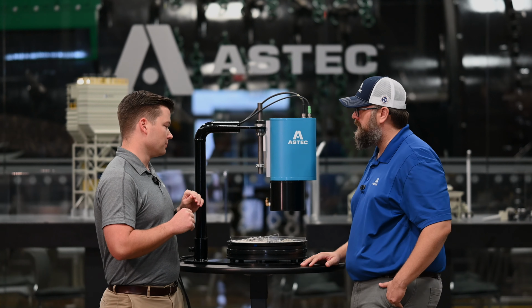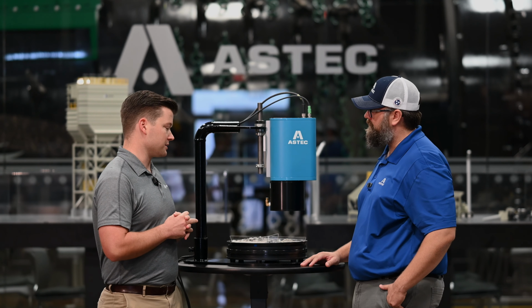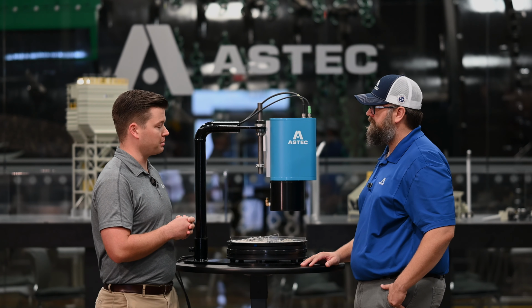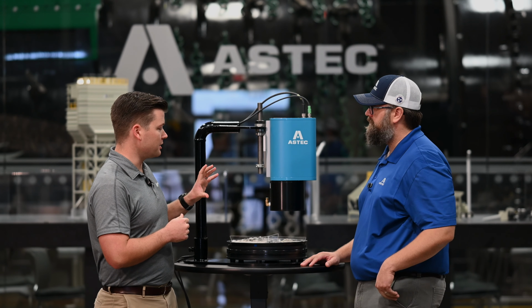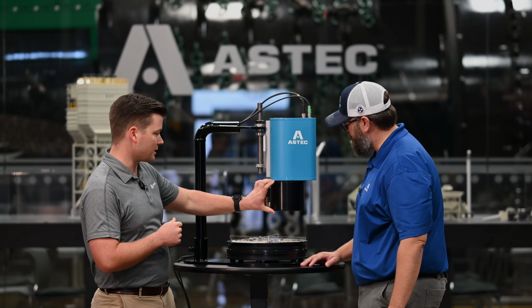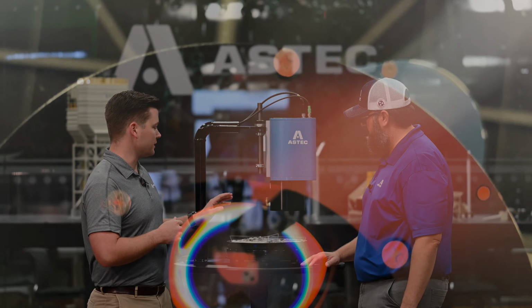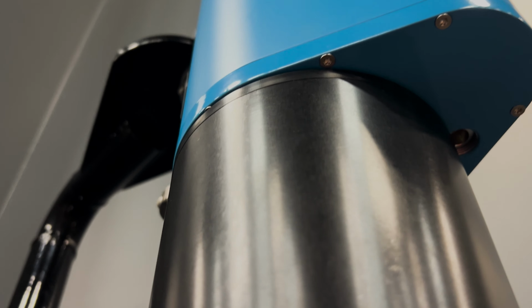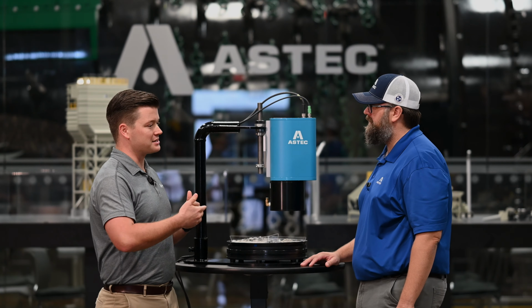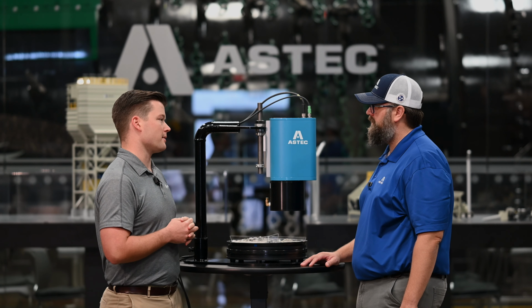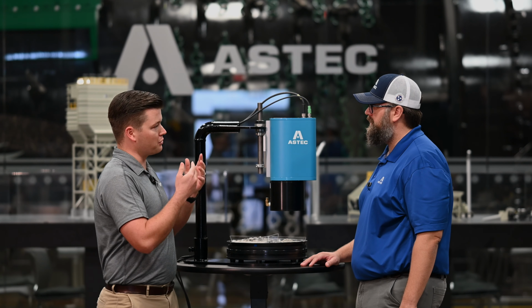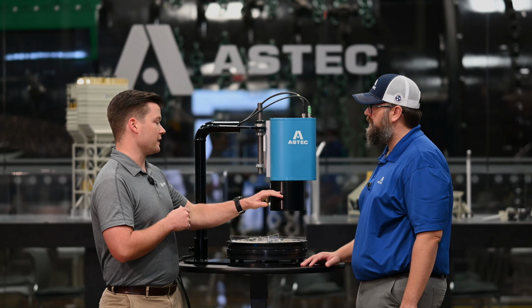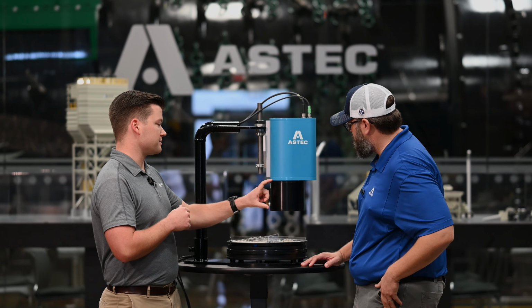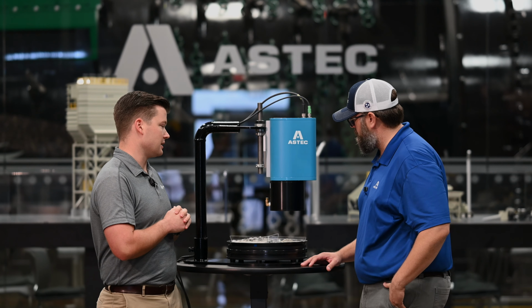The thing that impressed us most about this sensor was how rugged and survivable it is in an asphalt plant environment. One big contributor is this black portion at the bottom, which is actually a dust shield. We feed compressed air into a collar at the bottom of the sensor, providing a positive pressure environment just past the lens, which keeps dust, moisture, and other debris from coating the lens. That stuck out quickly, making this sensor really resilient and robust in that plant environment.